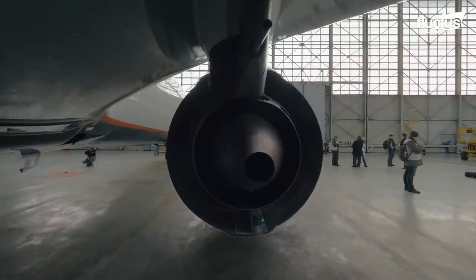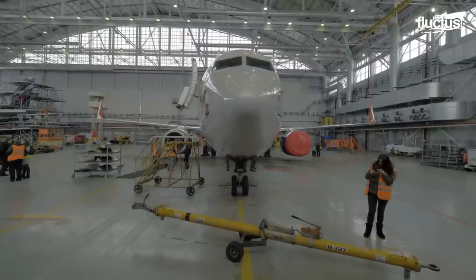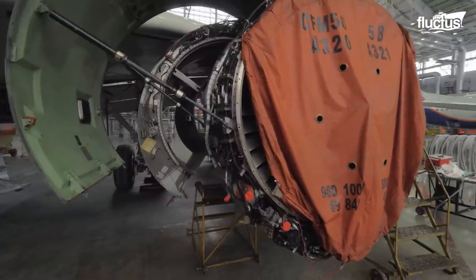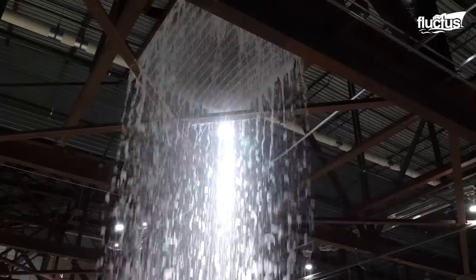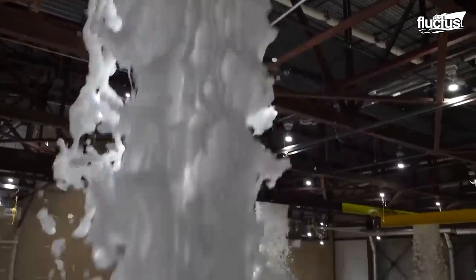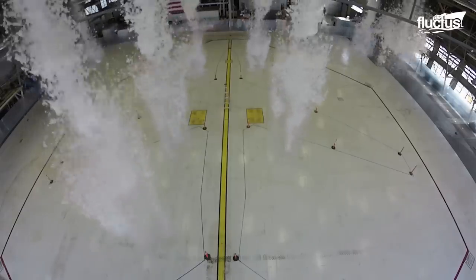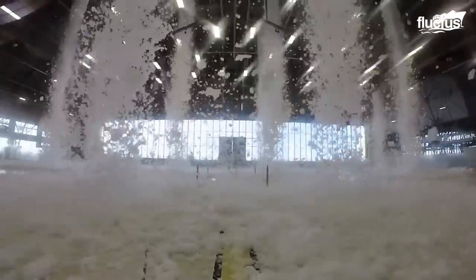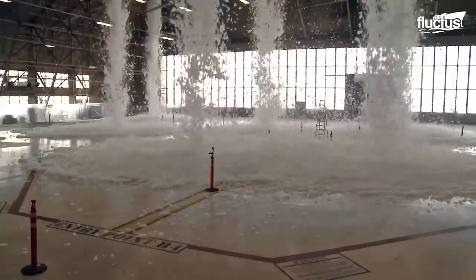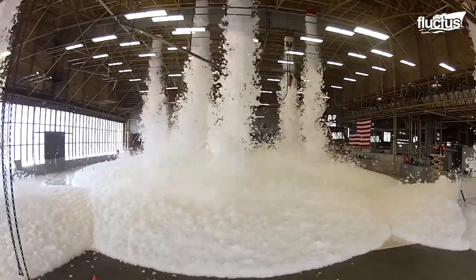This is because the flames can quickly spread from the plane to the structure and vice versa. So, to protect the millions of dollars worth of aircraft and equipment often stored in these hangars, many airports have implemented foam suppression systems in the ceiling. When triggered, these massive units release a special fire-resistant liquid which prevents the blaze from getting oxygen. It also helps coat any fuel that might have leaked from the plane, drastically reducing its flammability.